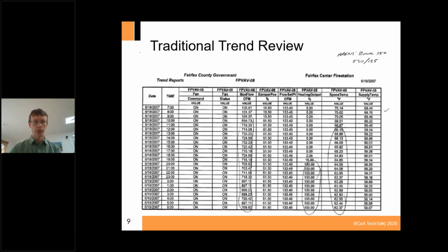This is a trend review from 2007, just a fan-powered VAV box. Fortunately this was a small building, a fire station, with probably only about 25 VAV boxes, so it was a quick review. Immediately the eye can spot CFM values going over our max, noted here as 530 max CFM and 135 minimum design. So if box flow CFM goes above 530, something's gone wrong, and we look at the damper position - 51%, and it's stuck there.